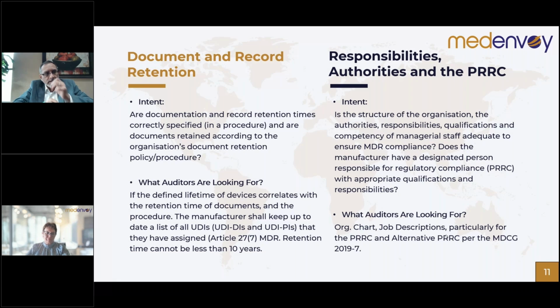Thank you, Danielle. And one point that I want to emphasize, even though the alternative or backup PRRC is mandated by Switzerland, not quite mandated in general by the MDR, a lot of notified bodies are kind of enforcing that anyway. So it's always a good idea to have identified the alternative PRRC and backup PRRC. Same as the PRRC, the qualification criteria, designation, and job description should have that information visible.